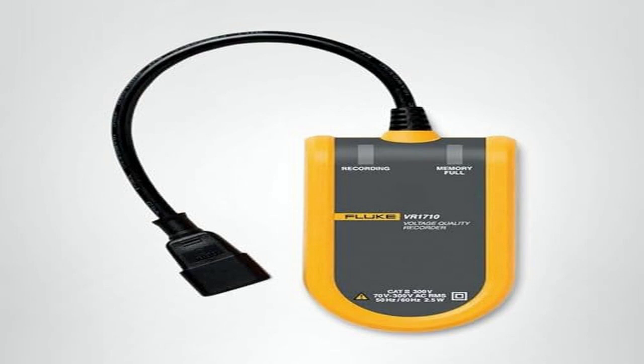The software side is where the practical strengths become apparent. When you plug the unit into a laptop via the included USB cable, the Fluke Power Quality Analyzer software pops up a graphical dashboard that highlights key events like overvoltage spikes, sags, and harmonic distortion without you having to dig through raw CSV files. For someone who needs to report findings to a non-technical manager, that quick visual summary cuts the reporting time dramatically. You can also zoom into any event, see the exact waveform, and export the segment for deeper analysis. It's not a full-blown data science platform, but it hits the sweet spot between raw data and a ready-to-present report.